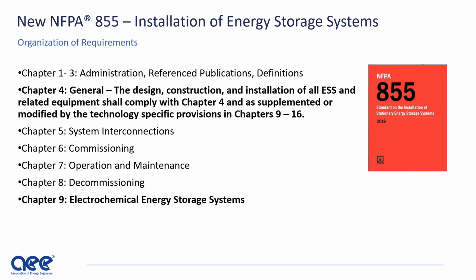I'm going to ask just one more for now, and then we'll move on with the presentation. Does the energy storage system come with power factor correction banks? The energy storage system does not come with power correction—it is strictly an energy storage system. If you want to include power factor correction, whether it's standard power factor correction, a harmonic-filtered power factor correction, or even solid state filtering, that would be separate from energy storage. That would fall into system design, but that's not what energy storage systems do.